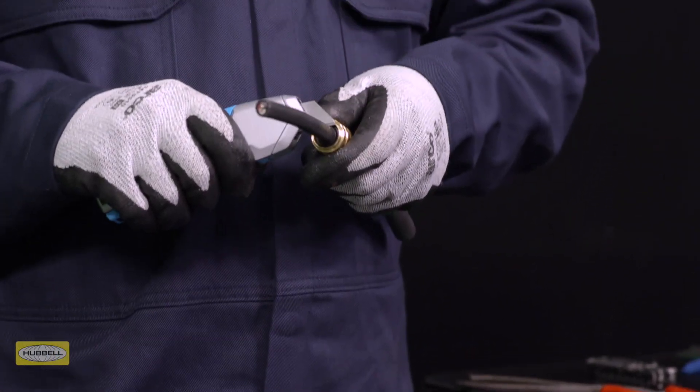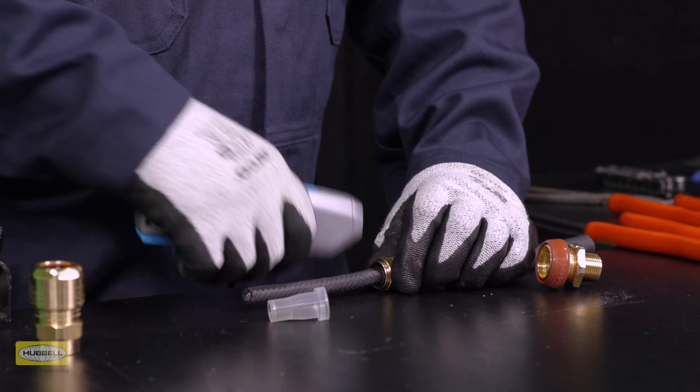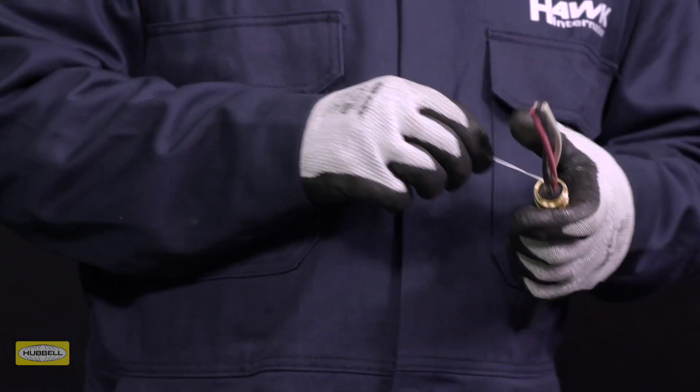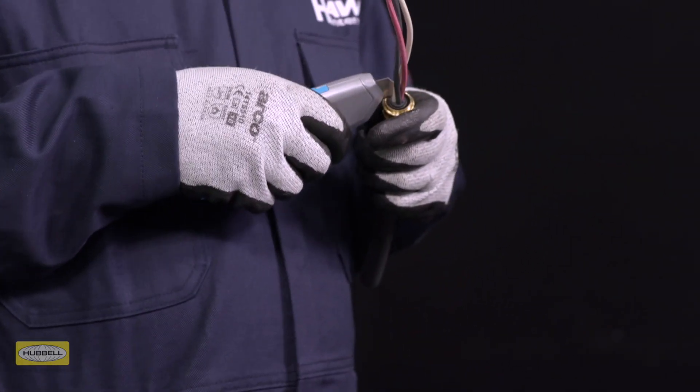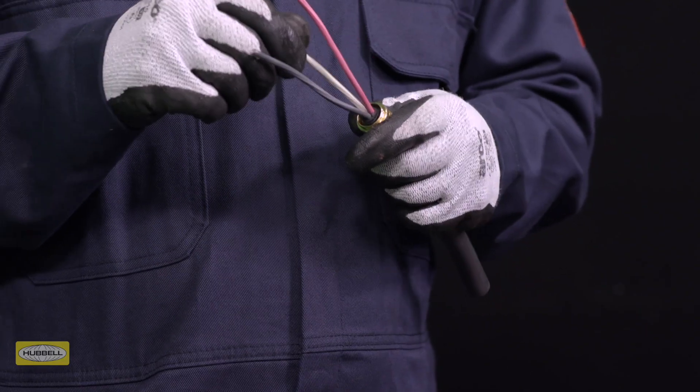Strip the inner sheath back to between flush and three millimeters from the end of the spigot. Remove any fillers, plastic, or coatings present in the cable. If required, prepare any drain wires or screens as per assembly instructions 2028.